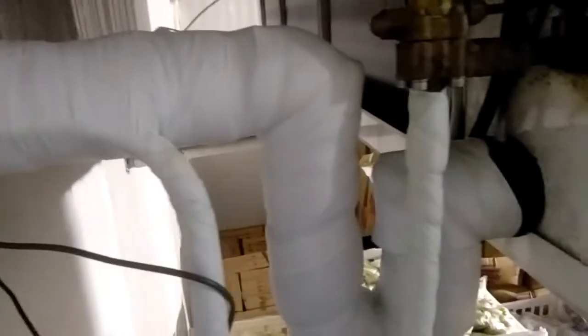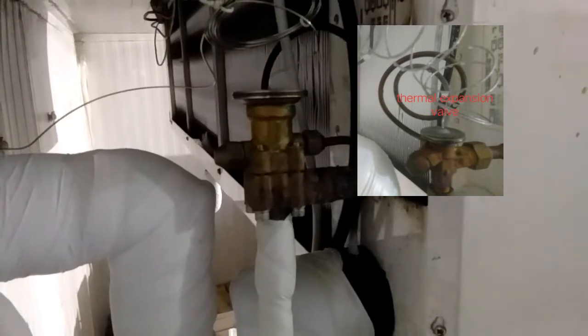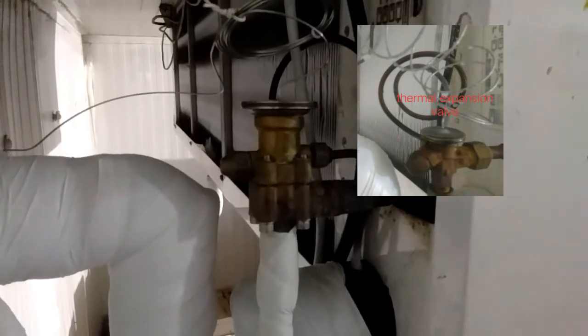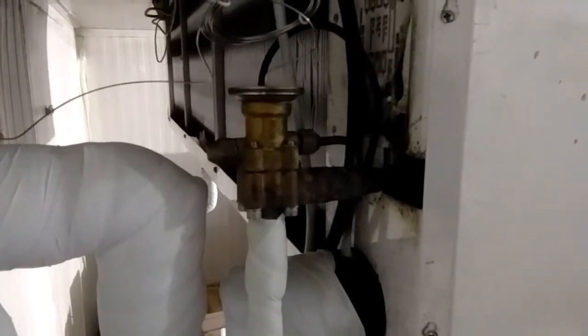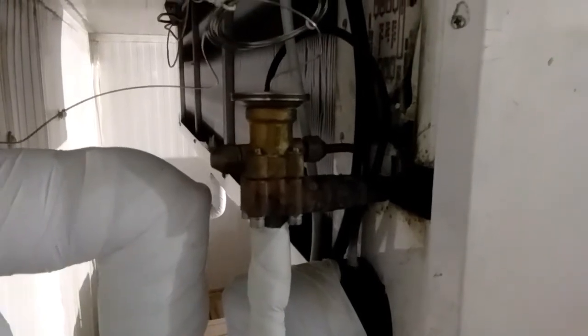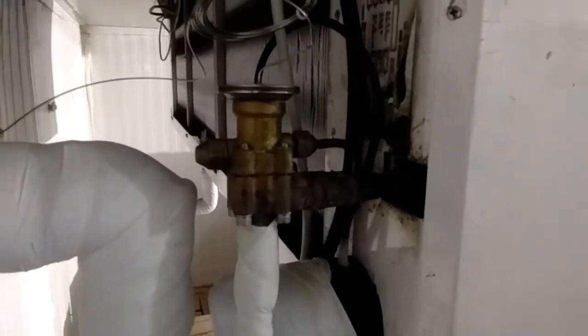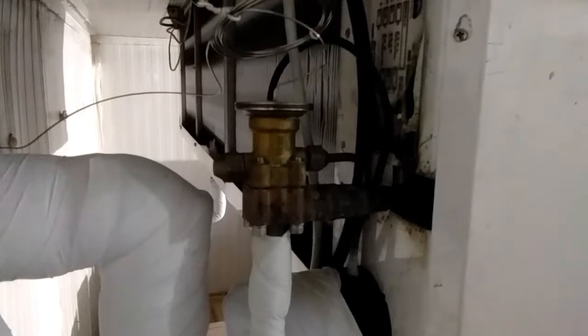As the refrigerant enters into the evaporator, usually every AC system has a thermal expansion valve. The TXV is also considered a variable switch to control the amount of gas entering into the evaporator. The TXV has a sensing bulb attached near the exit pipe of the evaporator. If the sensing bulb senses high temperature on the system, the TXV will allow more refrigerant to enter into the evaporator. If the sensing bulb senses low temperature, the TXV will reduce the amount of refrigerant into the evaporator.